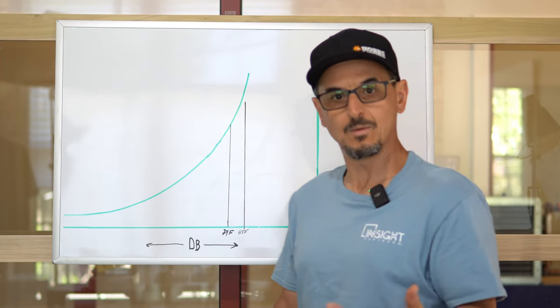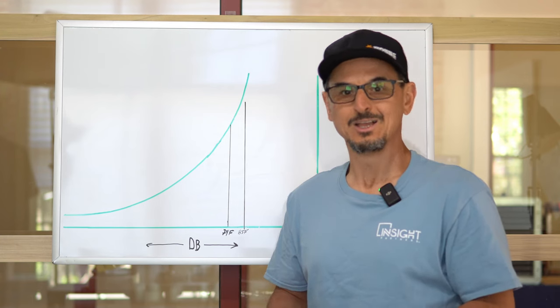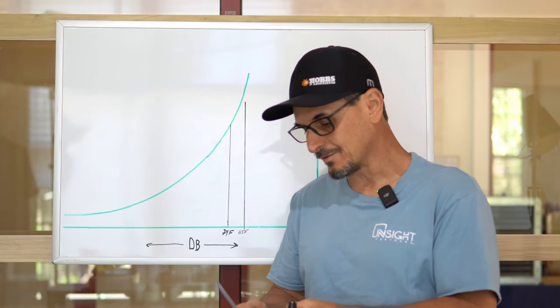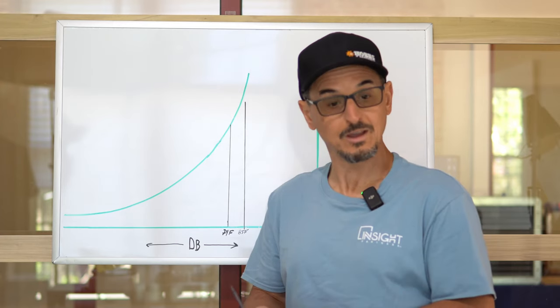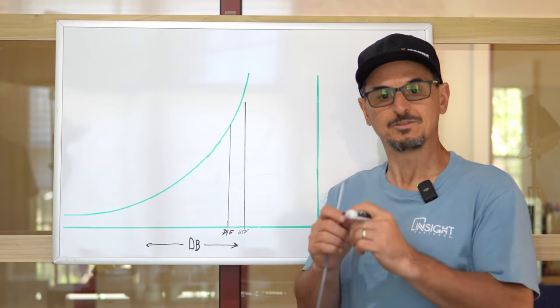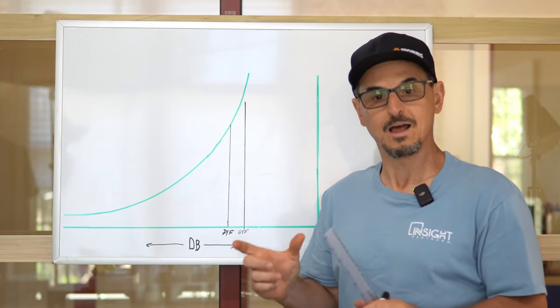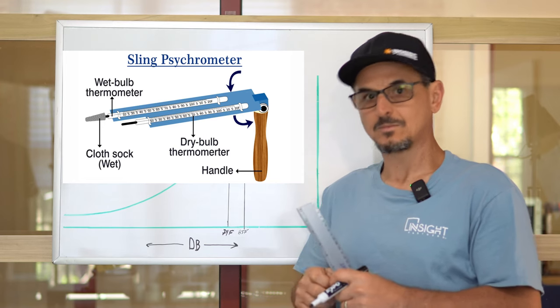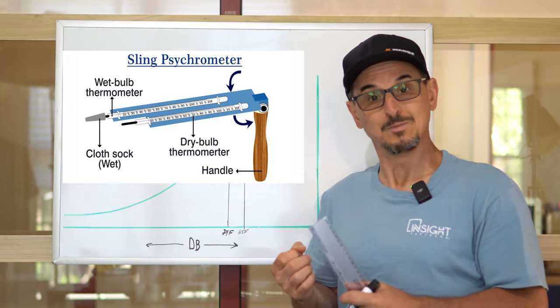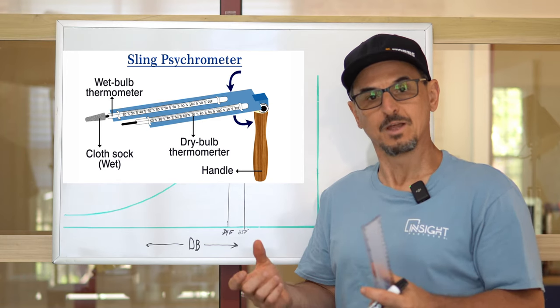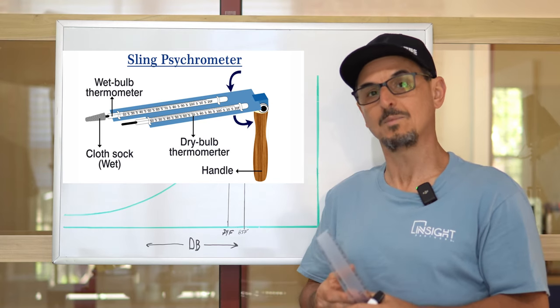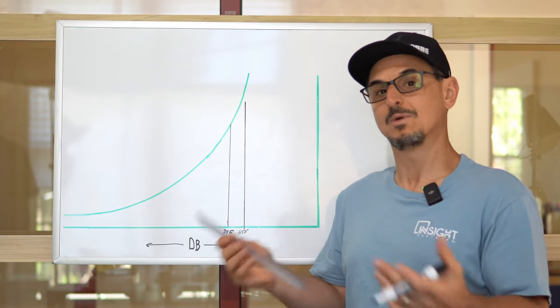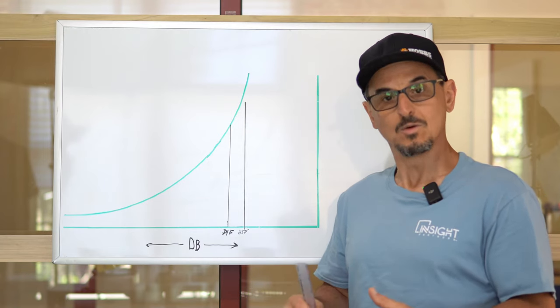Next, let's look at wet bulb. Wet bulb has to do with the moisture in the air. The way it's measured — it used to be measured with a thermometer that had a wet wick on the bulb. If the air is drier than that wick, the water will evaporate off the wick, provide a cooling effect, and decrease the temperature. So the wet bulb temperature is always lower than the dry bulb temperature. The higher the wet bulb, the more moisture in the air; the lower the wet bulb, the lower the moisture content.